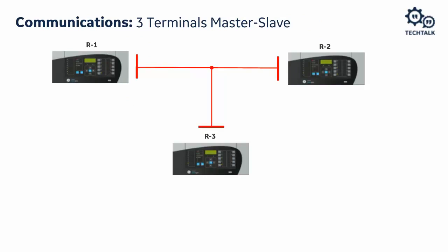When all channels are running, all relays communicate with each other and make independent decisions. If a fault is on the line, all relays trip individually — a big benefit of line differential is that we trip all breakers simultaneously, reducing or eliminating transients that can occur with sequential tripping. With distance, for example, one end trips and another trips via a pilot scheme 20 milliseconds later or more, causing current reversal transients. We stress the system less with current differential because we trip simultaneously.